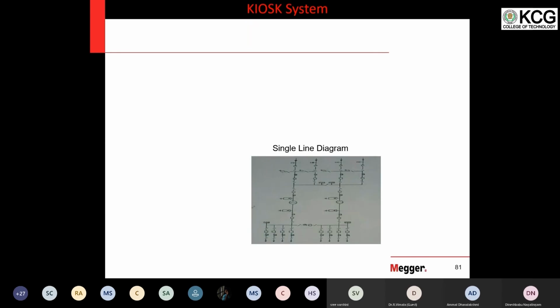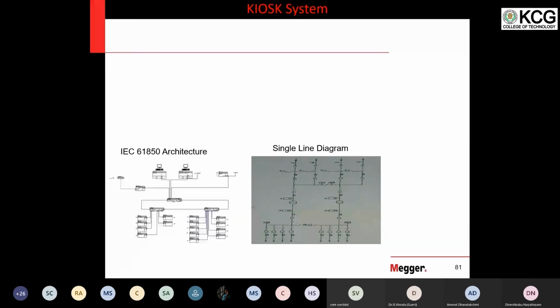Okay. Now this is a very, very important slide. It's like a climax for all the things that we have been discussing for the past 1 hour. We are going to conclude. A single line diagram: 4 230 kV incoming lines, 2 auto transformers, 8 110 kV lines. Okay. We already saw the architecture. 2 switches at bay level, 230 kV, 110 kV, fiber optic cable, and this is the station switch connected to the SCADA system, GPS and LDC for gateway. Okay.